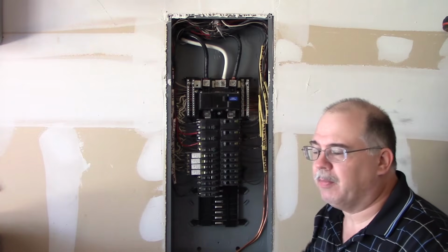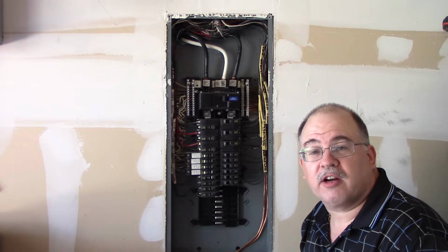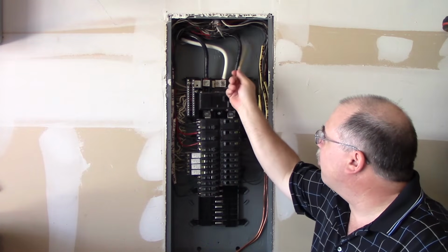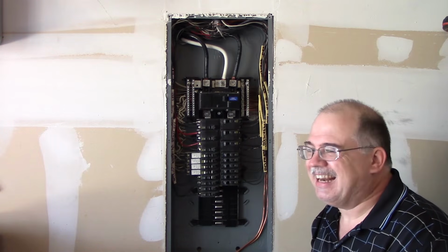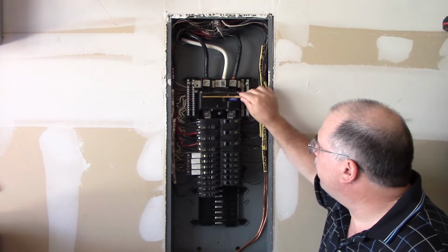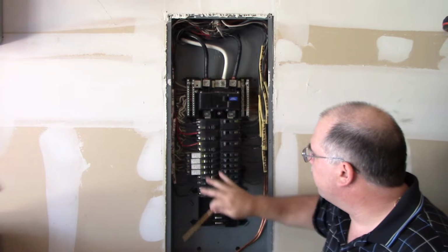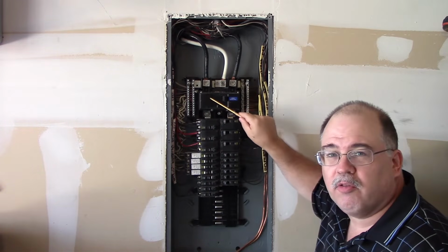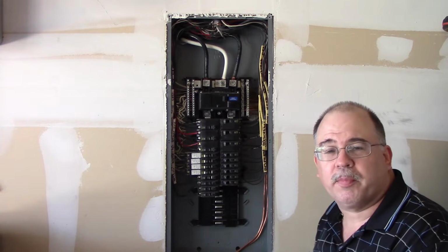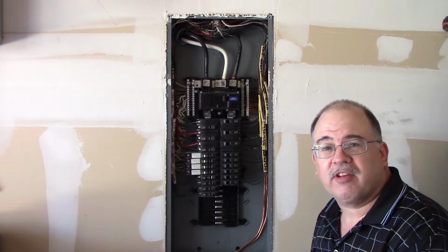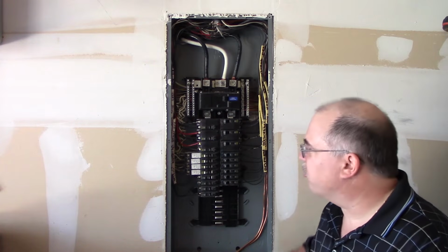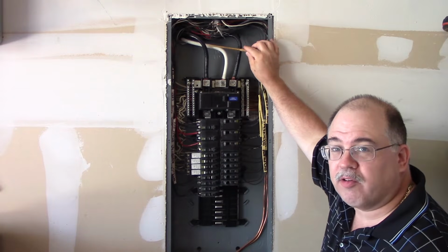Okay, so the conductors coming in are these service entrance conductors, and that's only providing overload protection, not any other protection. Now, from this point down, all of the components down here are being protected by this overcurrent protective device. And again, overcurrent devices protect you against short circuits, ground faults, and overloads. Okay, so these conductors aren't protected except for the overload.